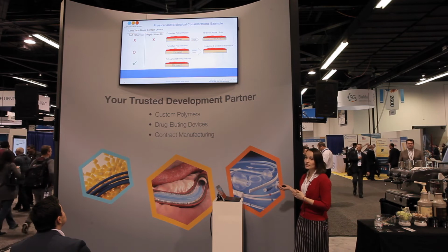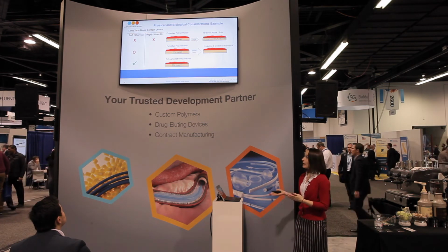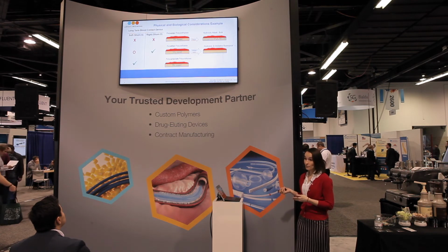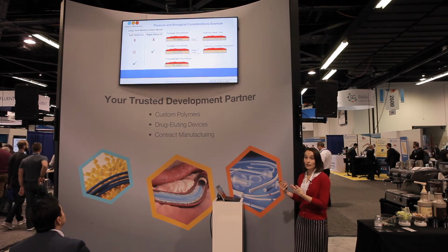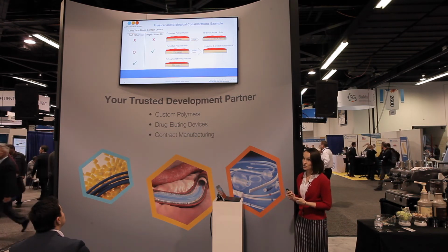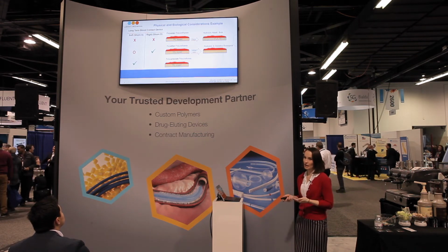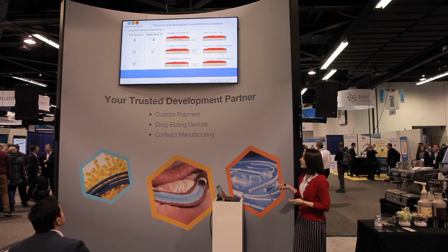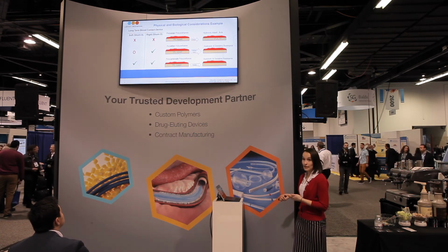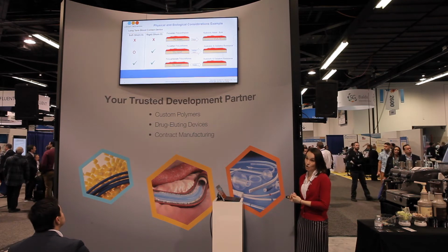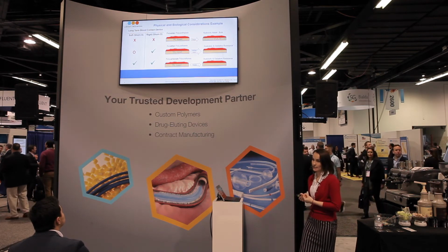Now, a higher hard segment of the material in a Shore D product of a polyether is going to be more stable. So it may be a good product for a stiff application for long-term blood contacting, where a softer application may or may not be acceptable. And in the last example, a polycarbonate-based material is going to be a good option for both hard and soft applications for permanent blood contact.